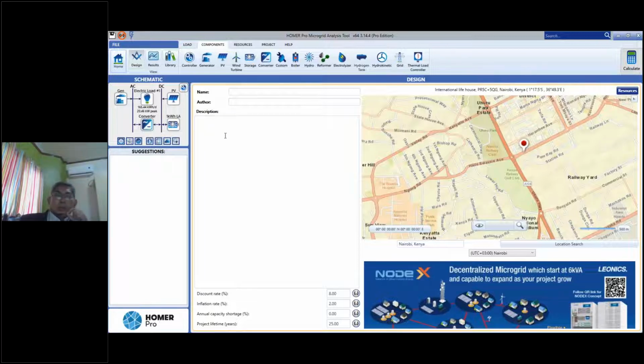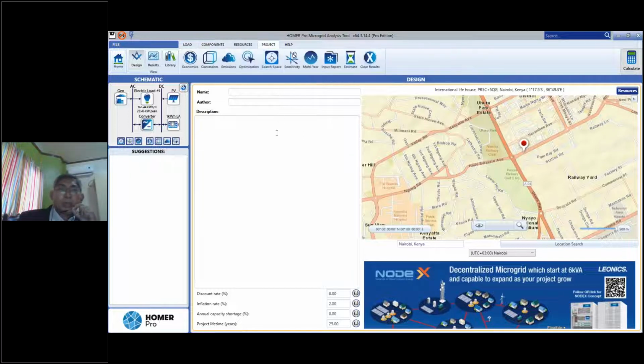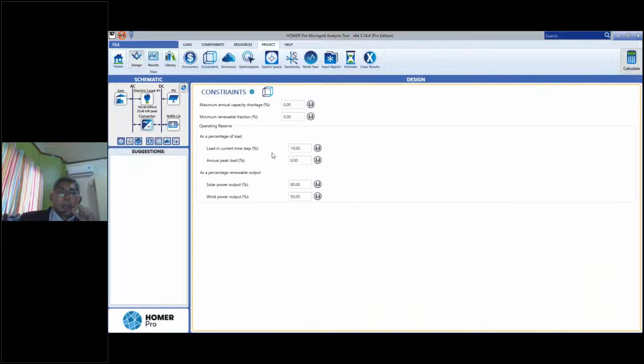So we can look into the system reliability because, as I've shown earlier, the genset only system was running at 8,760 hours. Well, that's quite unrealistic in the real world. So what if we allow a downtime? That means part of the load will not be met. That happens, and even the grid code allows that. So we can look into the project and click on the constraints. On the top, you can see maximum annual capacity shortage. For the initial run, we're using 0. That means there are no outages and all the loads are met.